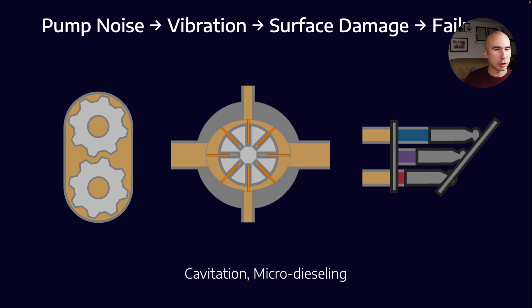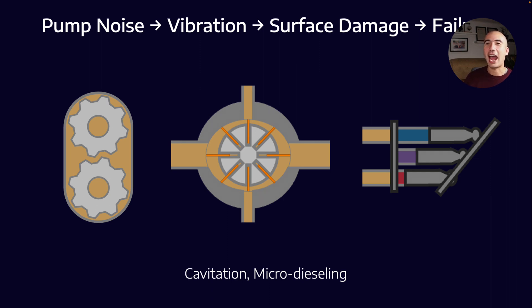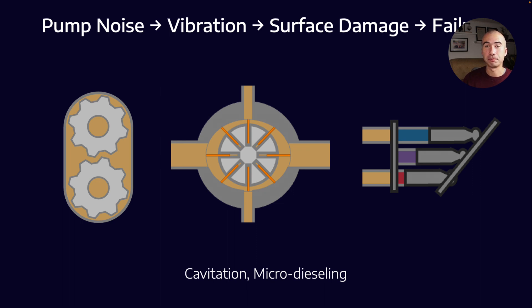This presents itself a couple of ways — sometimes it's cavitation, sometimes it's micro-dieseling — but the effects are broadly similar, and the sound is also broadly similar. I describe it as someone gargling marbles. When you walk past a pump, it'll sound like there's a whole bunch of marbles in the system. You either have a cavitation problem or a micro-dieseling problem.